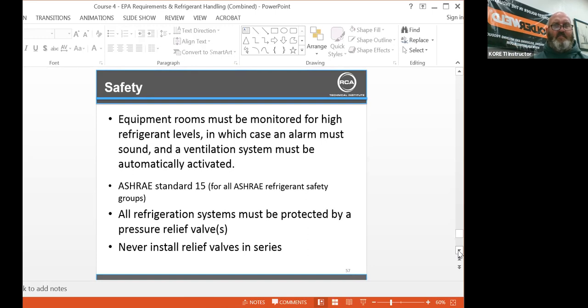Safety: equipment rooms must be monitored for high refrigerant levels, in which case an alarm must be sounded and the ventilation system must be automatically activated. I've seen that a lot in Albertsons locations. It's got that little refrigerant sensor on the inlet side of an evap condenser fluid cooler. So it's monitoring the intake, especially when the evap condenser is inside the store or inside the mech room. You'll see it there. ASHRAE Standard 15. You have to follow that for all ASHRAE refrigerants.